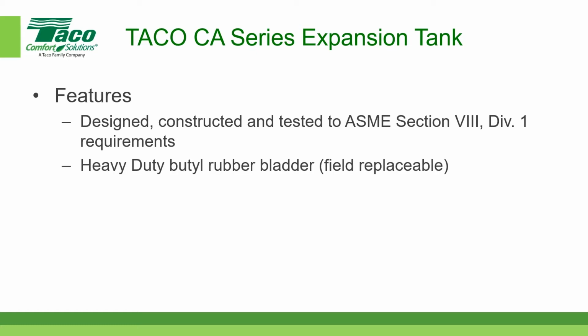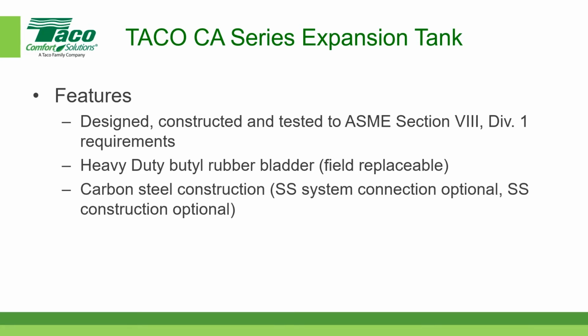The bladder itself is a heavy-duty butyl rubber bladder. That's something to consider. It's pretty common, very flexible, forgiving. It's field replaceable, and if installed correctly, these bladders should last upwards of 20 years, 15 to 20 years installed correctly. Please keep that in mind.